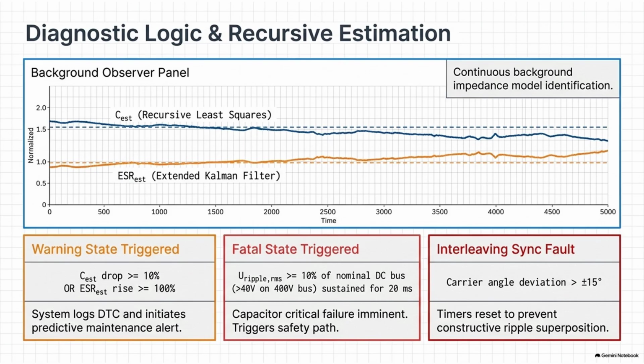The specs mention recursive least squares and extended Kalman filters. I mean, these aren't just reading data. They are inferring physical reality from electrical behavior. Right. To understand how these algorithms work, you have to look at system identification theory. The algorithm cannot physically measure the capacitance or the resistance inside the sealed box. Because it's locked away. Right. But it knows exactly what the inverter is doing. It knows the exact timing and magnitude of the electrical stimulus it is applying to the system. And thanks to our high-speed extraction circuit, it can see the exact voltage ripple response. So it compares the stimulus to the response.